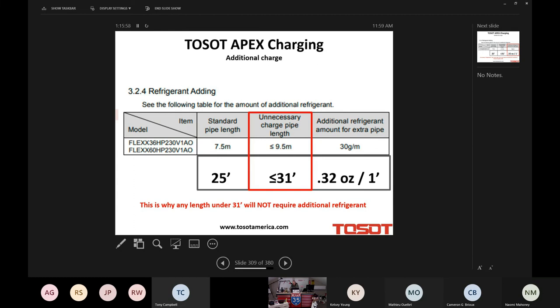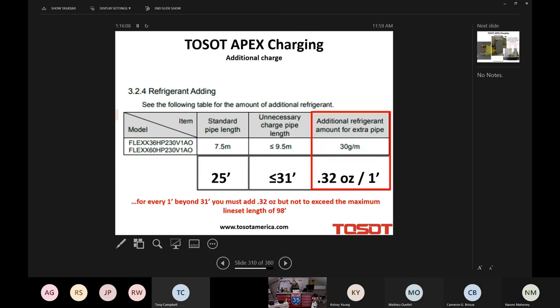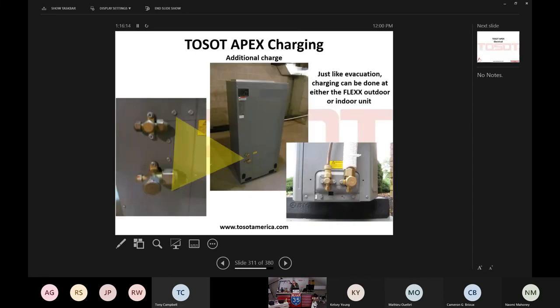So if you're utilizing the two pieces of equipment as a system, anything between 15 to 31 feet, you're good to go. Right? But you can go to 98 feet. And if you do, again, you're going to add 0.32 ounces for every additional foot, not to exceed 98 feet. And it will be weighed in. Much what we do in our mini split world.